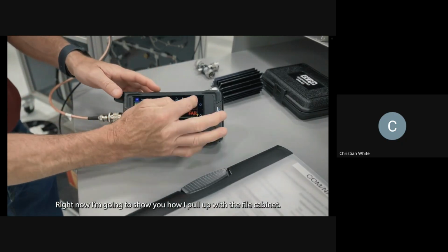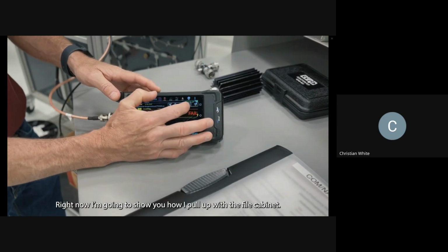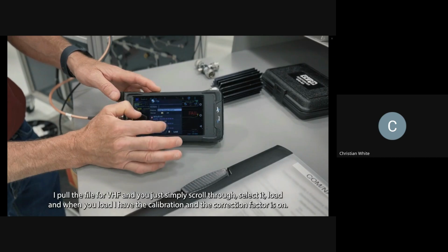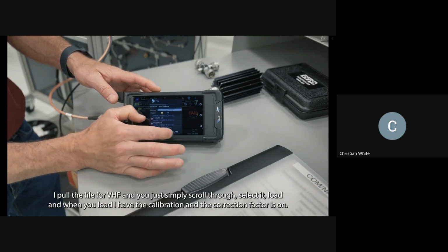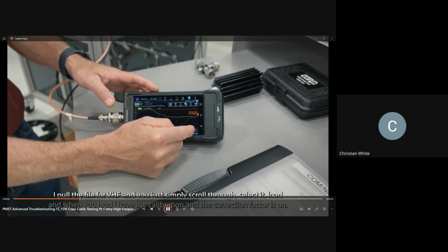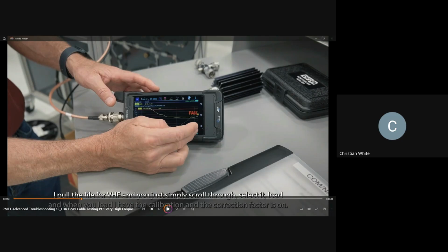Right now, I'm going to show you how I pull up the file cabinet. I pull the file for VHF. And you just simply scroll through, select it, load, and when you load, I have the calibration. So that's what we talked about when we first got into using that Sitehawk, is loading that file. So what we did is we inputted the information manually that may or may not be saved in that Sitehawk. And I would rather have you guys get used to putting the information in manually, because depending on the Sitehawk that you get from Atlas, or if you happen to have the one that B1 owns, whether or not that information is going to be there. So I just wanted to point that back out.